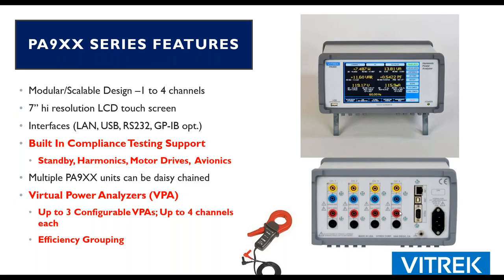Each one of those VPAs can be configured from 1 to 4 channels. So what I'm going to do to explain that a little bit better, that really helps with our efficiency groupings and our efficiency calculations. So for example, I could take just the 3-phase motor. I want to take the input of that, and I'm going to apply phase 1 to channel 1, phase 2 to channel 2, phase 3 to channel 3, and I'm going to assign that to VPA number 1, for example.